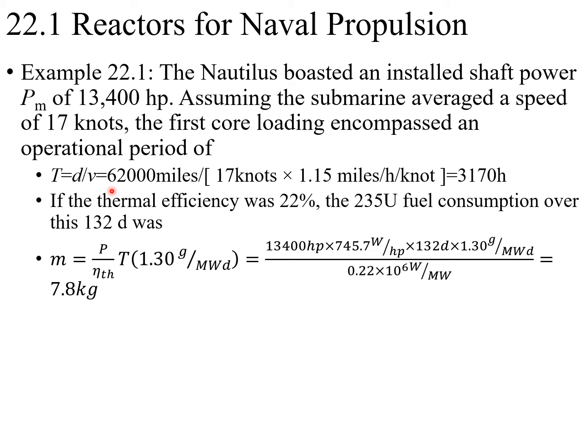We use the shaft power divided by the efficiency to get the thermal power. We use 13,400 horsepower, then convert it to watts, since 1 horsepower equals almost 750 watts, divided by 22% efficiency. Then times 132 days, times this coefficient, then divide by 1 million to convert watts to megawatts, so that we get a total fuel consumption of 7.8 kilograms.